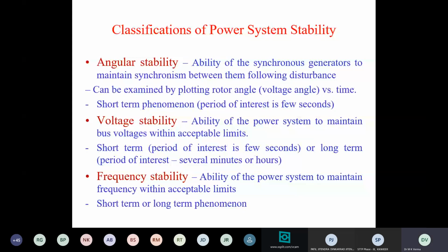Voltage stability is a load-driven phenomenon. It is the ability of our system to maintain bus voltage within acceptable limits. We have different loads connected to different buses. So we have to see, if load increases or decreases, what will happen to voltage? Voltage rise or voltage fall. So following a load increase, voltage may decrease. Or following a load increase, voltage may also increase, provided it is a radial system. If it is not radial, it may go either way. It may either increase or decrease.